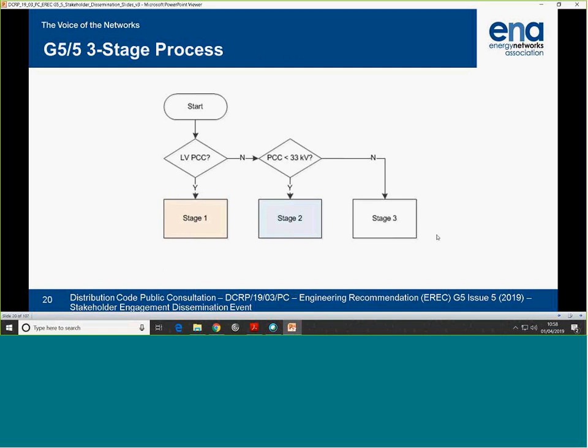At the simple level, it's a three-stage process. Stage 1 looks at the low voltage point of common coupling. Everyone here knows what that is, but if not, it's the point, going from the customer to the source, at which another customer could connect or is connected. If you fail stage 1, you can go into stage 2, which I'll explain later. Stage 2 covers voltages below 33 kV, typically 11 kV, but also going up to traction, as Drew said. Some network operators have 20 kV or 22 kV systems, and we still have 6.6 kV, so the range aspects are covered.